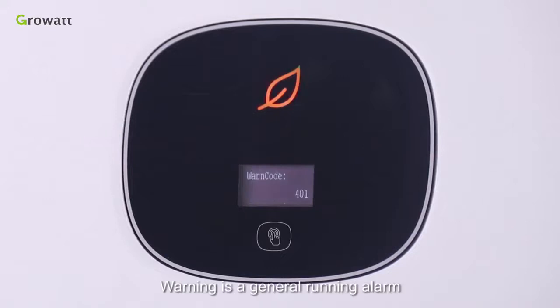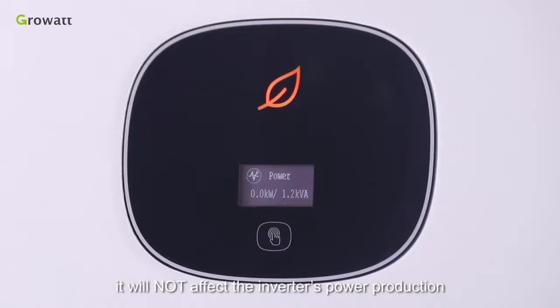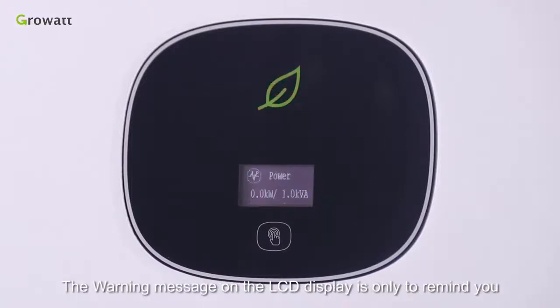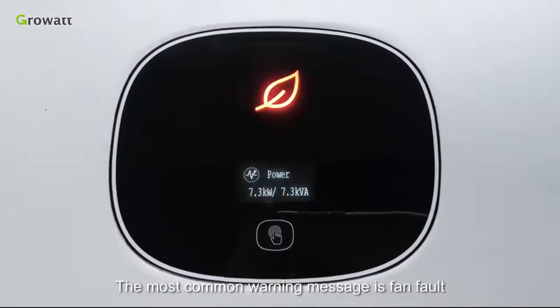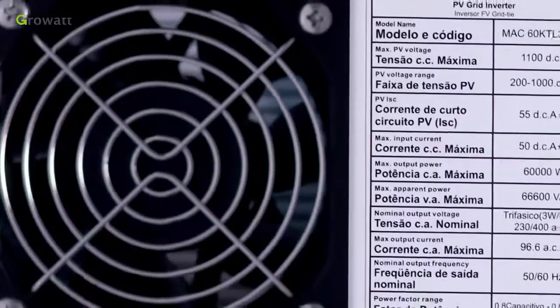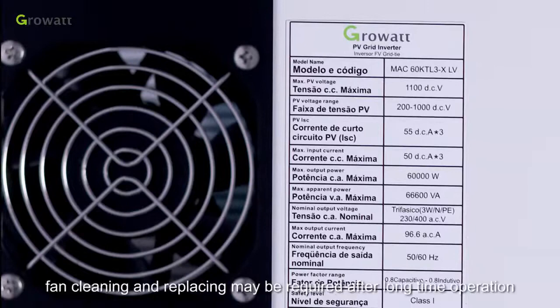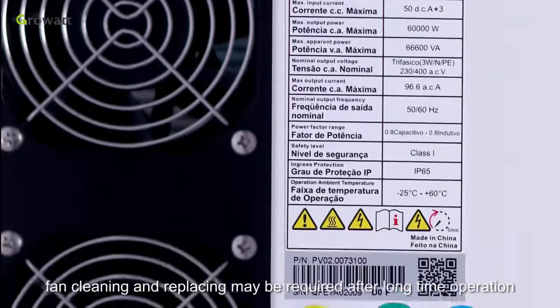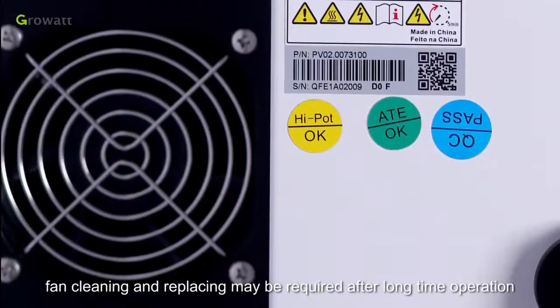This warning is a general running alarm. It will not affect the inverter's power production. The warning message on the LCD display is only to remind you. The most common warning message is fan fault. As a wear and tear part, fan cleaning and replacing may be required after long-time operation.